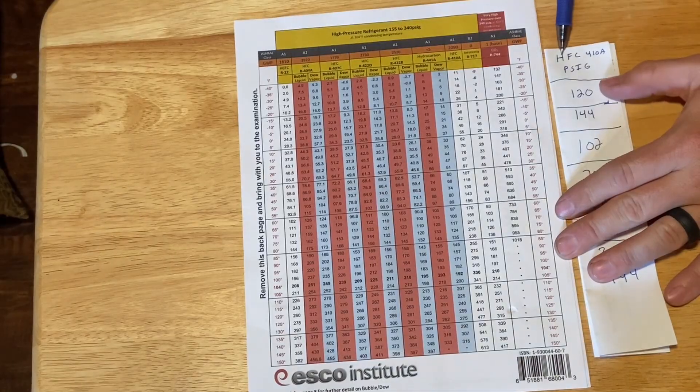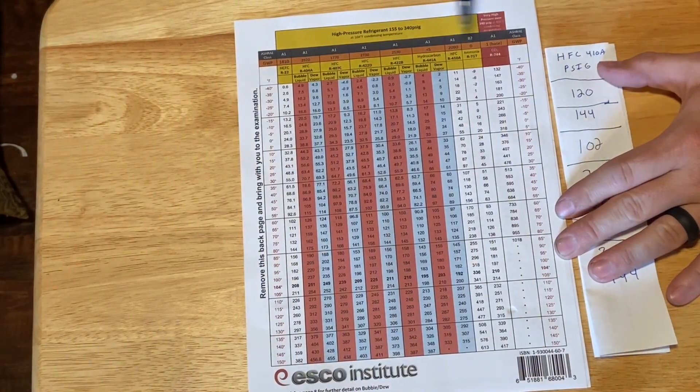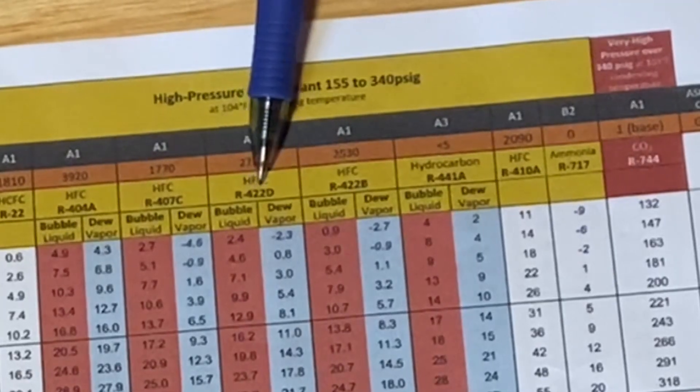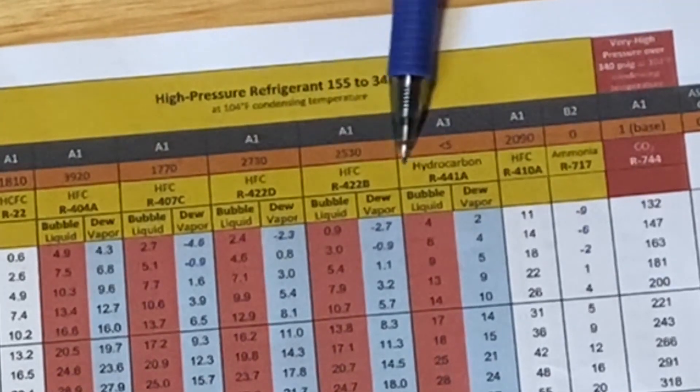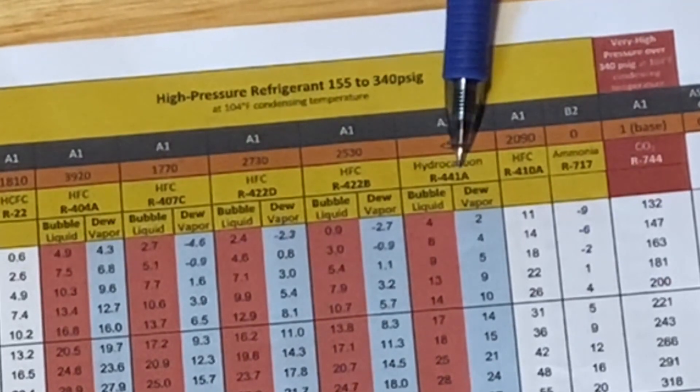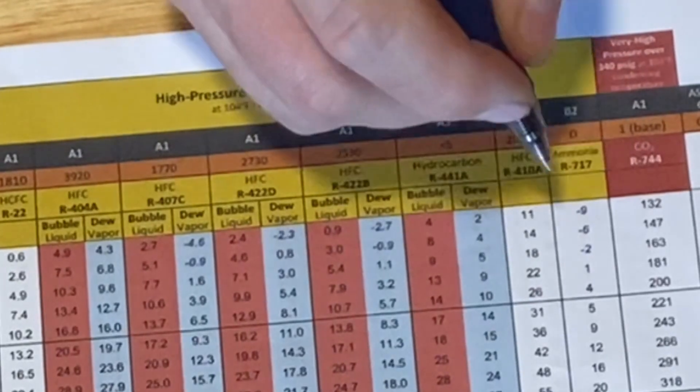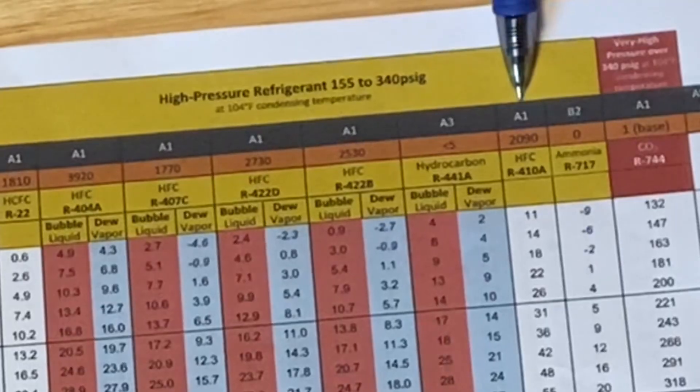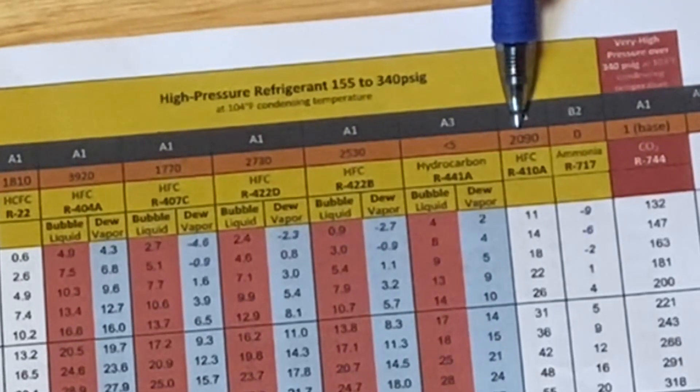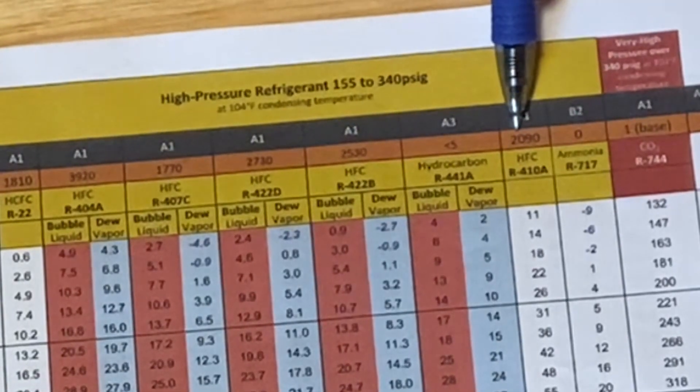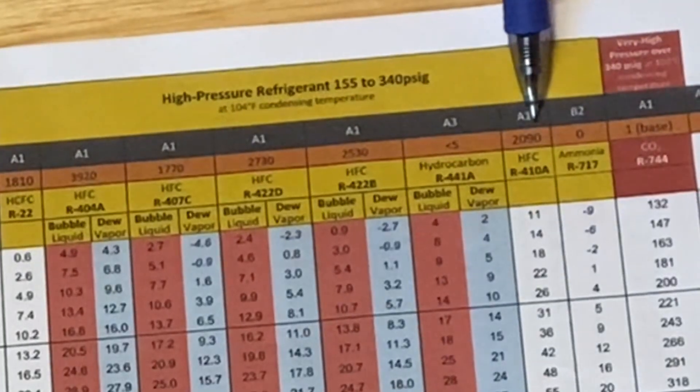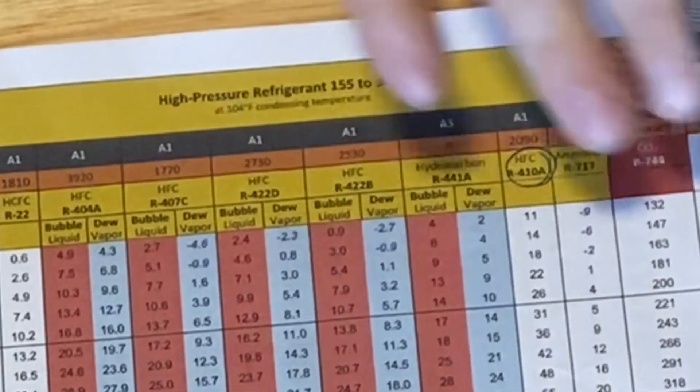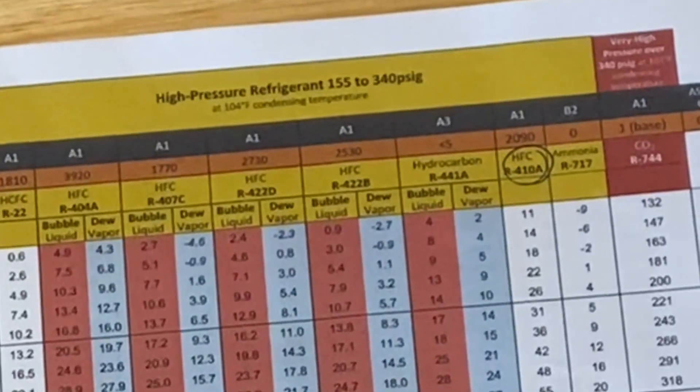Okay we're gonna work these together. So we'll start out with HFC 410A. So we're gonna look on our chart. Here's 22, 404A, 407, 422D, 422B, R441A, and here we go. This is what we're looking for in HFC R410A. It tells us it's an A1 refrigerant, global warming potential of 2,090 times greater than CO2. We'll get to those later but we're gonna circle this so we know that this is the line that we're looking for.